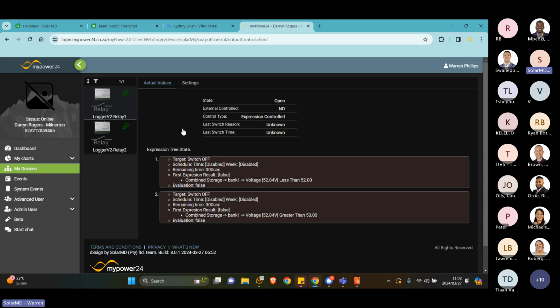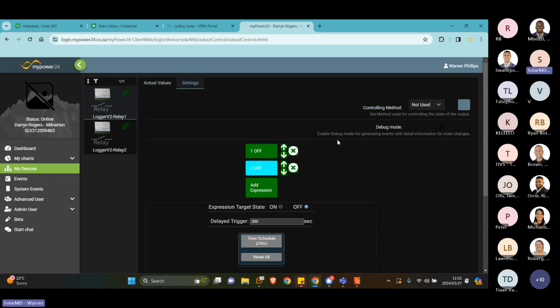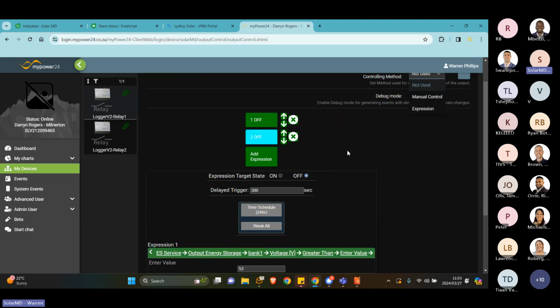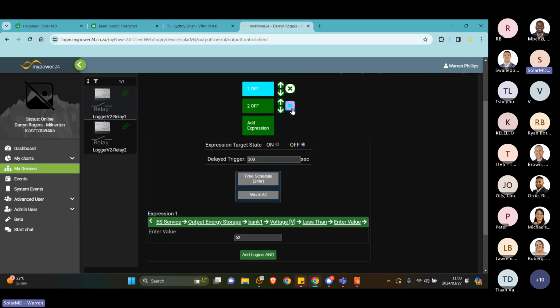You can use these relays in two different ways, or not use them at all. You can manually trigger the relays by switching them on and off, which can be configured, or you can automate that process. So here you would configure the relay rules, saying you want to control this relay via an expression, and this is where you would define what those expressions are.